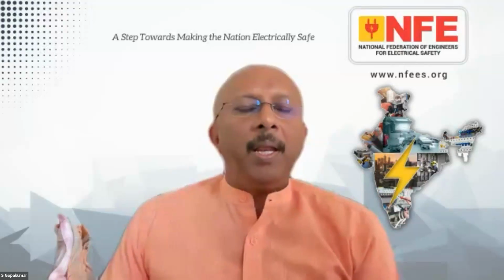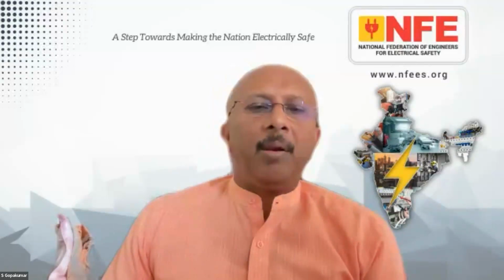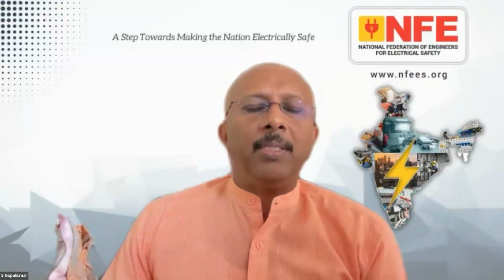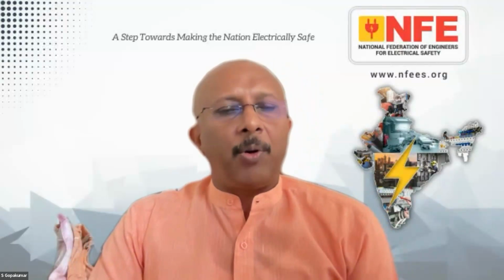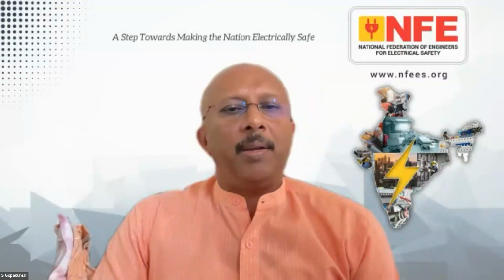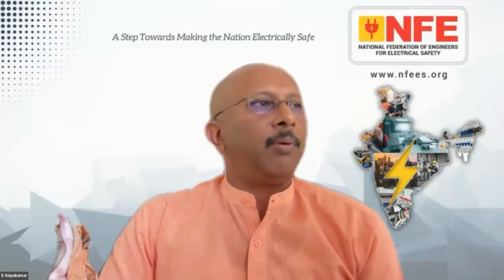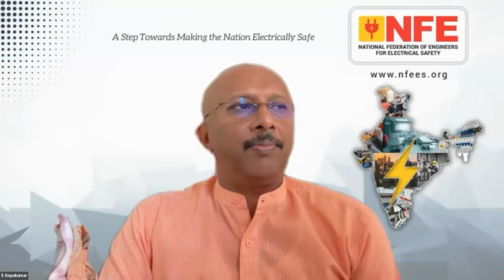Actually, Mr. Davis, this 10 milliampere and 30 milliampere are not related. 30 milliampere is the RCD requirement for personal protection in a normal, dry condition, for a dressed person. 10 milliampere is the maximum allowed leakage current from an electrical apparatus.